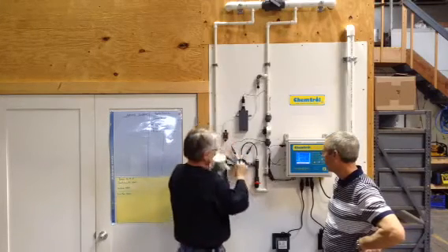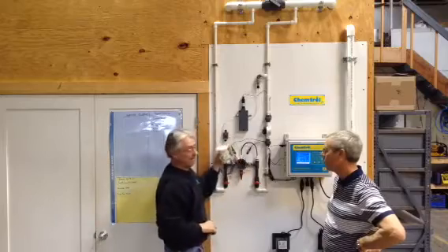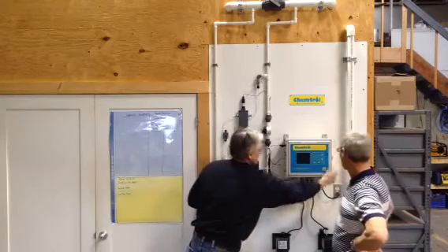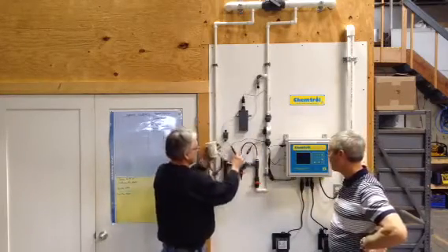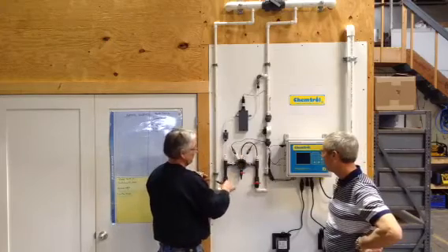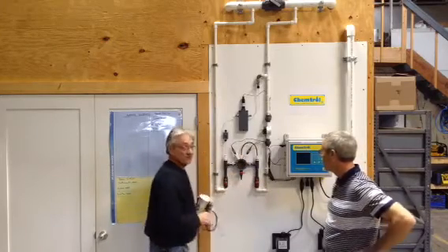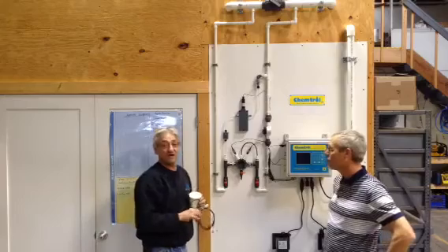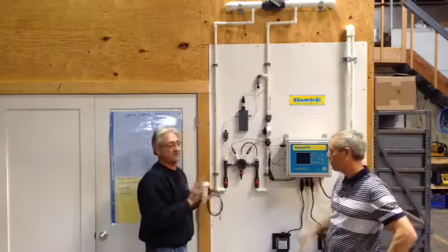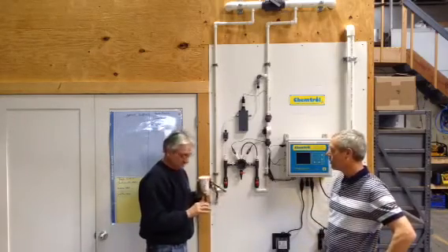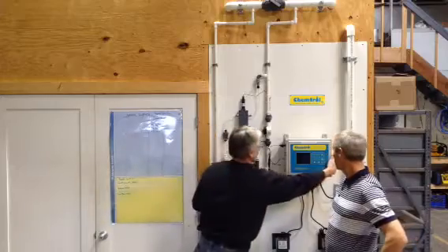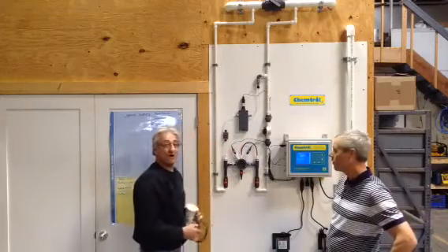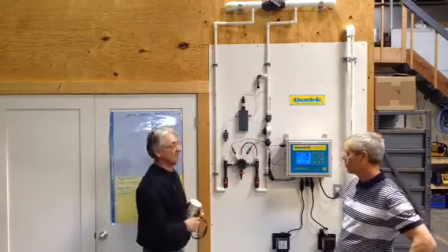And when you're doing this, you're going to have to flush this for a little while. So when you do that, shut your controller off, and when you put the probe back in, you're going to open up the lines and let it flush for about 20 minutes before you turn your controller back on. Because when you've cleaned them, everything's going to be out of calibration. So after it's about 20 minutes, turn the controller back on, test your water, balance it, and then calibrate your controller.